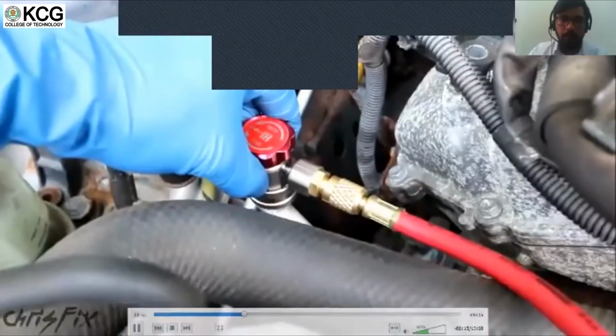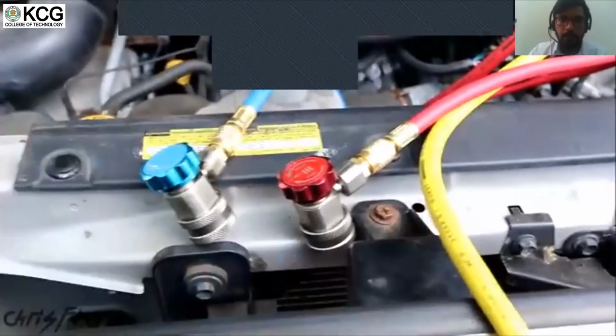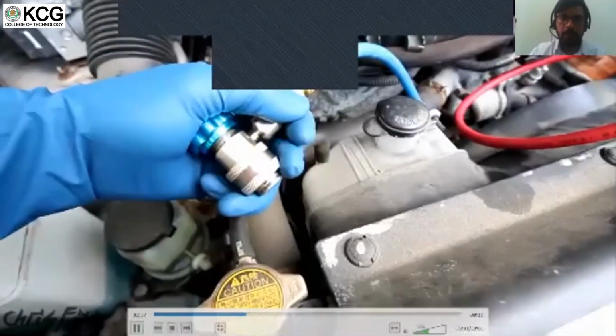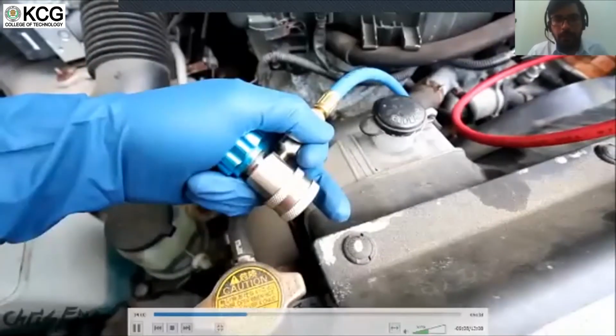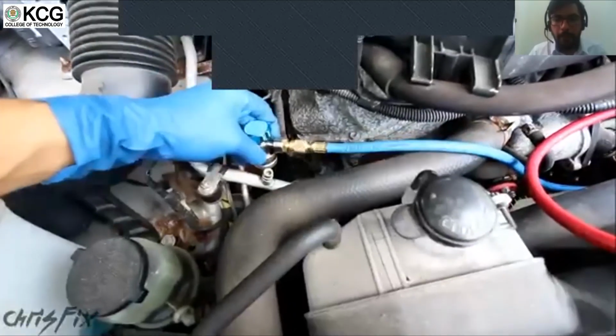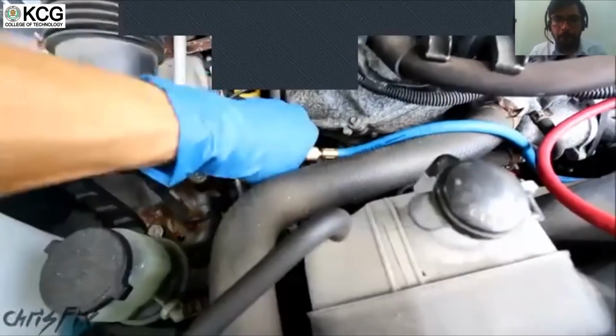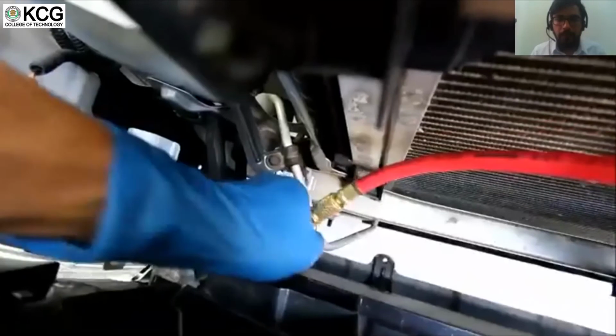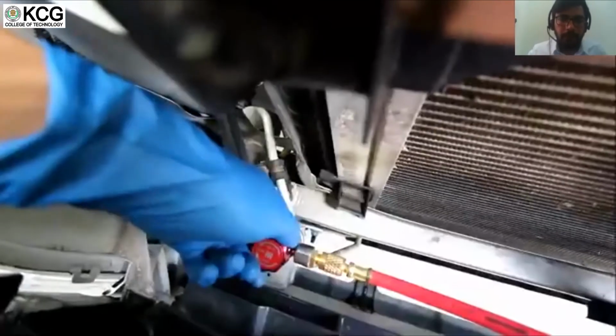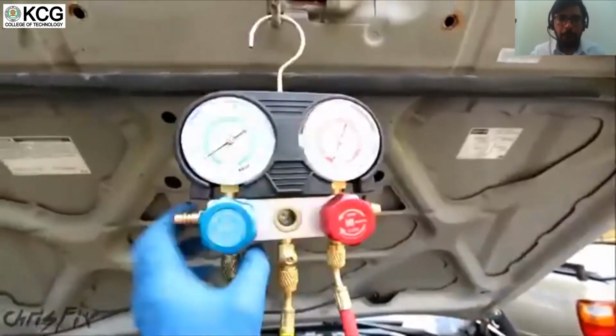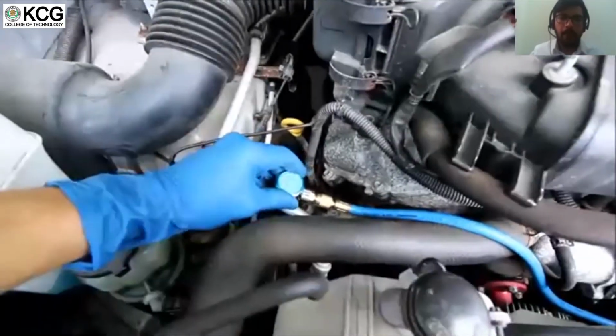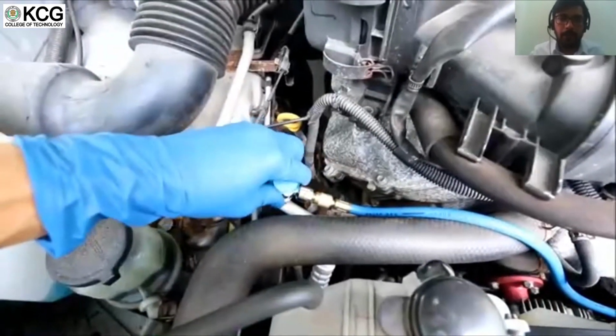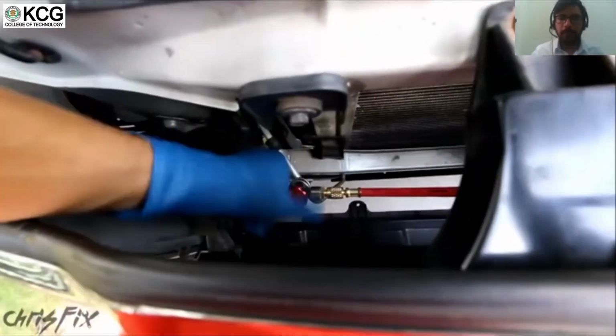It does not fit on it, so you don't have to worry about mixing those up. To connect these adapters, you just push down and slide it over and then let go. And we're going to connect our low pressure, which is this blue line, to our low pressure port right here. Make sure it's in there good. Get our high pressure line here, which is the red, and we're going to connect it right down here to our high pressure port. Good. Now back at our gauges, again, these are closed off. We're just going to come over here and open these up. Open the low pressure side. Good. And open the high pressure side.